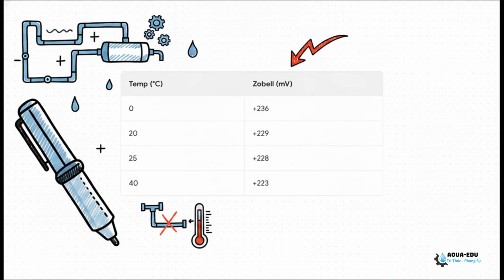I want to bring this temperature point back up because it is without a doubt the most common mistake made on the floor. Always, always remember to use your temperature compensation chart if your equipment doesn't have automatic temperature compensation. Just look at the variance. At 0 degrees Celsius, ZoBell is plus 236 millivolts. But at 40 degrees, your target drops all the way to plus 223 millivolts. If you don't account for temperature, your offset is going to be inherently flawed, and you are literally putting the entire RO membrane at risk.